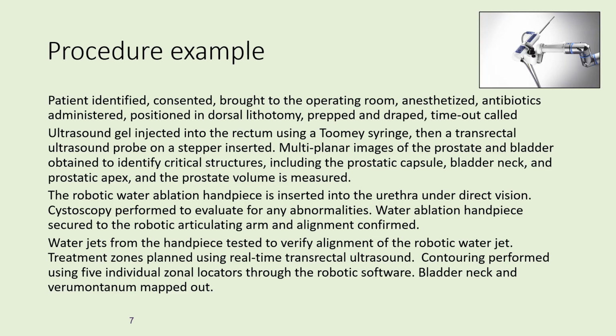Then the robotic water ablation handpiece is inserted into the urethra under direct vision. Cystoscopy is performed to evaluate for any abnormalities that may be problematic for the procedure. Once everything's shown to be in good position, the water ablation handpiece is then secured to the robotic articulating arm and alignment is confirmed. Water jets from the handpiece are tested to verify alignment of the robotic water jet.